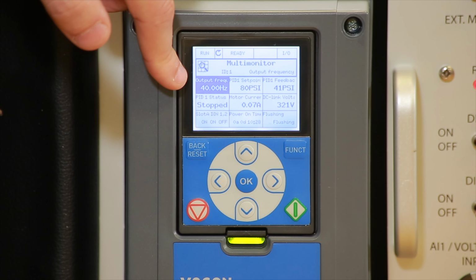Now, here is an application wizard: you can run this drive many different ways. The standard way of running a drive is with a PLC. However, if we don't have a PLC, if we're running this drive standalone on a wall with a pressure transducer, which is the case right now, instead of a standard application, we're going to pass by the HVAC application that we can also run, but PID control. So the drive has a PID controller inside it, so we don't need any external PLCs or pump controlling relays. This is the beauty about this drive.